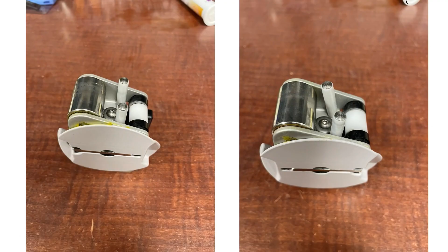And one of the things that happens with some of our components is that, again, there are methods to actually unstring your blood pump segment. There's a little button that lets you, and all machines are the same way. But what's the faster way? You start a lawnmower. You put your foot on the machine, and boom. And we know they put their foot in the machine because why? We've seen footprints on the machine. And what happens is that these roller guides bend. We have seen incidents where the roller guide has literally ripped the blood pump segment and leaked into the machine. So please, when you get back, tell your staff there is a method of doing the right things.